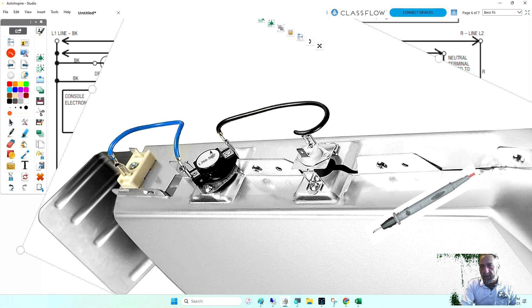So that's what this information is. This is the limit, 260, with a 50 degree cut in. This is what we call cutout. It opens up at this temperature, cut in, it closes at this minus 50, 260 minus 50, so it'd be 210. Okay? Guys, if you know the temperatures of a thermostat, you could be within 5 degrees. If you got a spare thermostat that's 145 on your truck and the customer's machine was 140, you're good. You can put that one on there. Don't have to be the manufacturer one. As long as it's within 10% of the temperature there, and it doesn't really go over 160, which is on the exhaust housing. Always on the heating element, it's a high limit thermostat, except for GE. GE puts some operating thermostats on their element, so it's the only one, they're the oddball.